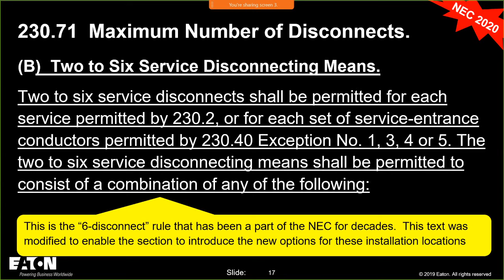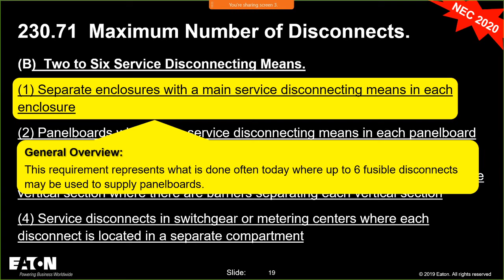The first option is basically having separate enclosures. We'll typically see this when we have 6 fusible disconnects, right? You'll see 6 fusible disconnects or 6 breakers, enclosed breakers. And what's nice about that is each one of those enclosures has an overcurrent device in it. It has a switch in it. You can barrier off the line side. And if you're using the 6 switches or up to 6 switches, then those switches are going to be serving a panel board, which gives you an additional benefit of the overcurrent device giving you lower incident energy at that first panel board or whatever the equipment is.